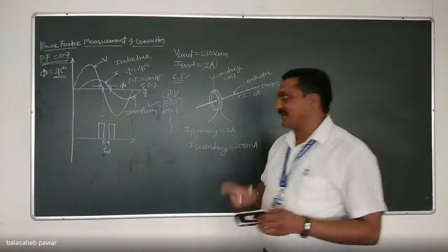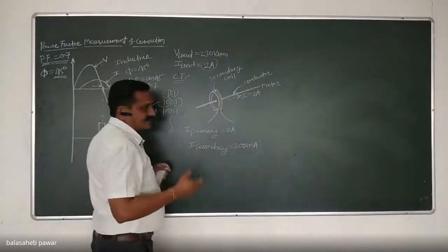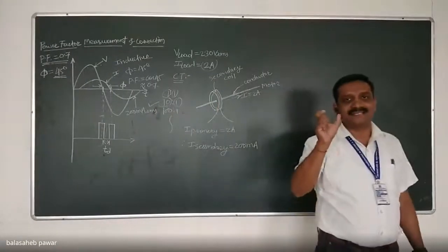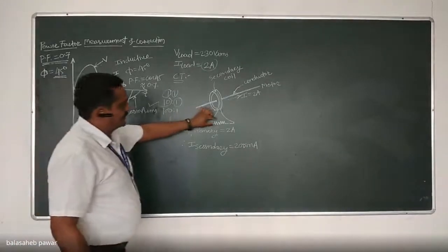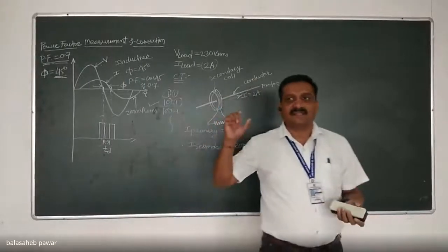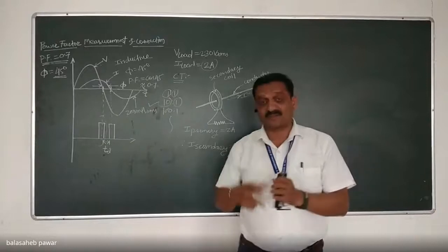No, it is somewhat complicated. So instead of that, remember that CT comes with somewhat low resistance across its secondary terminal. Low resistance, okay? That means there is a resistor connected across the secondary coil as shown, and that resistance should be as small as possible, because this coil itself is acting as a current source, but it is not that strong a current source right now.